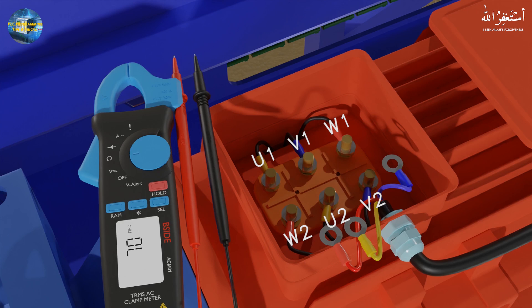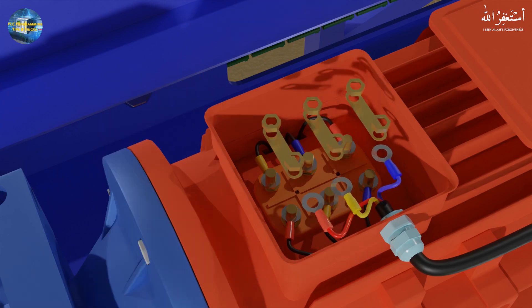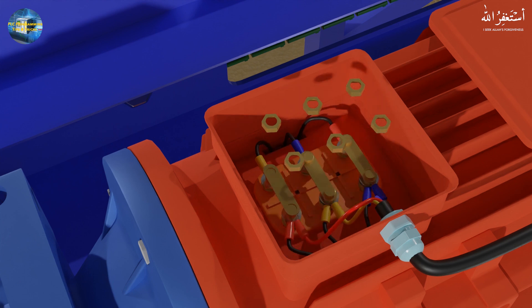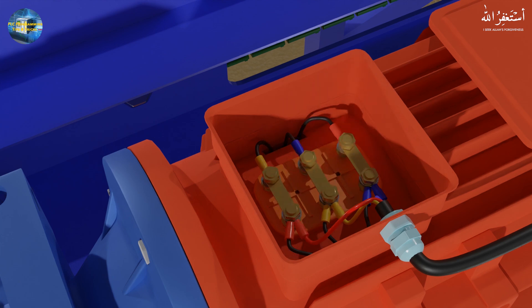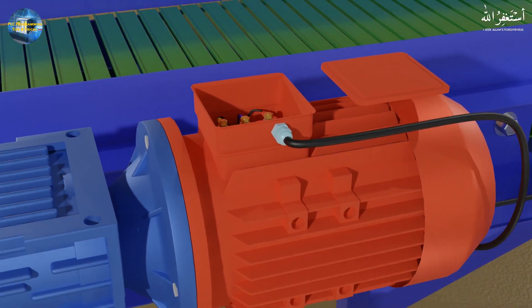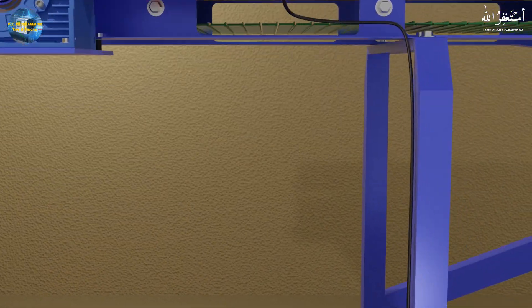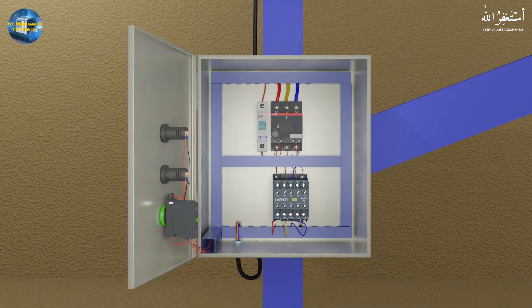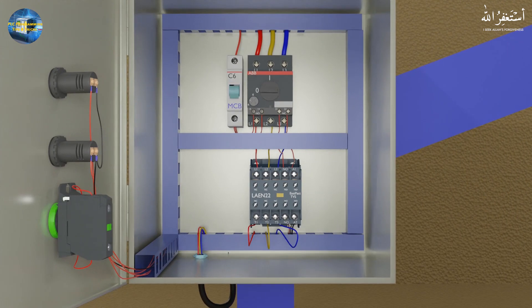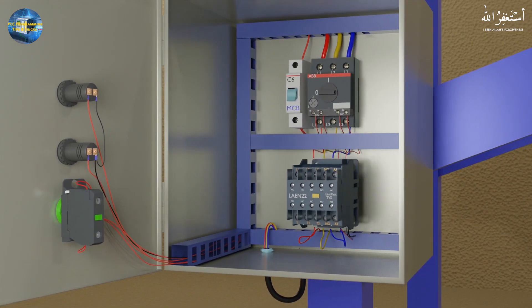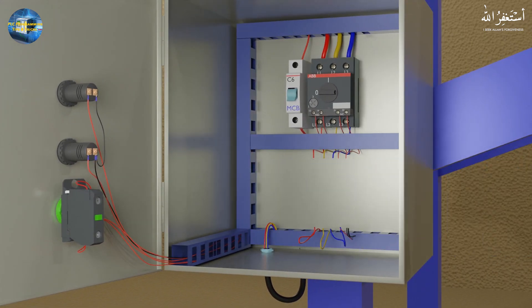Now we have confirmed that the motor side is okay — there is nothing wrong with the motor winding. So we will connect all the windings back to the motor terminals. Next, we will go back and check the contactor, as one of its contacts may not be passing current to the motor winding coil, causing the current imbalance across the motor windings.